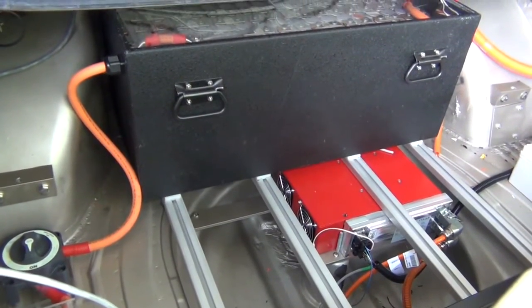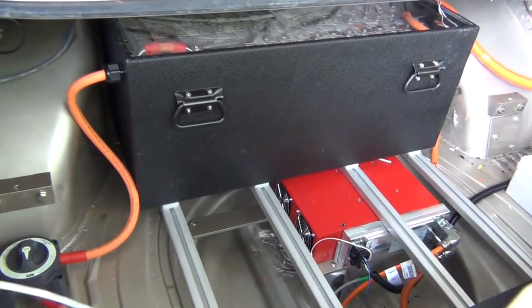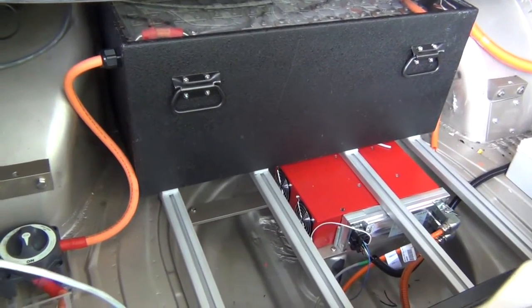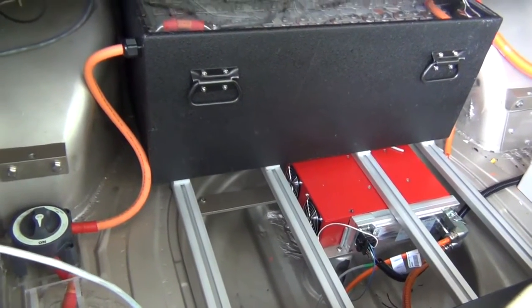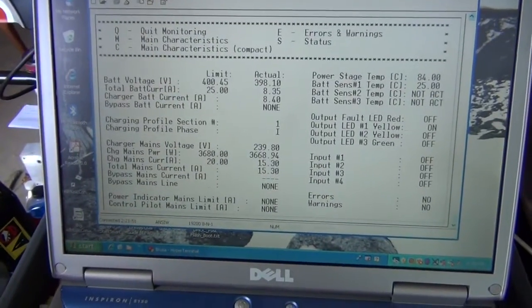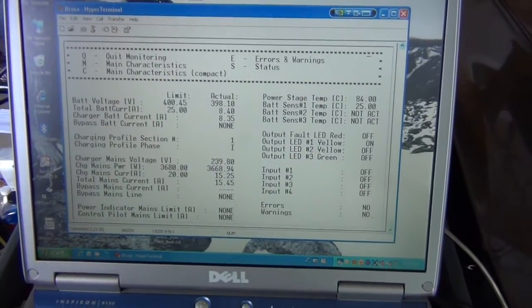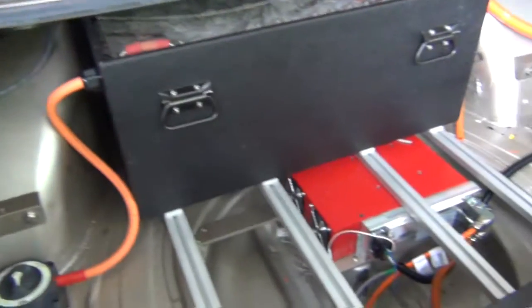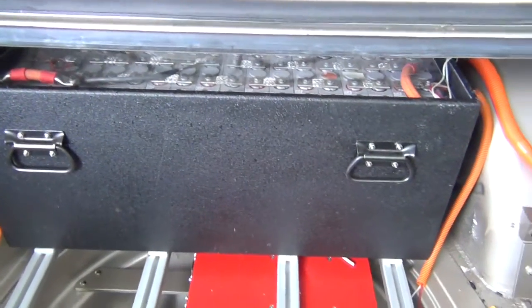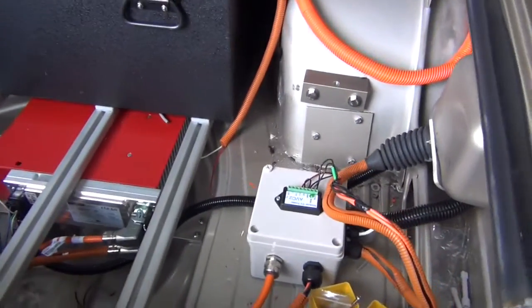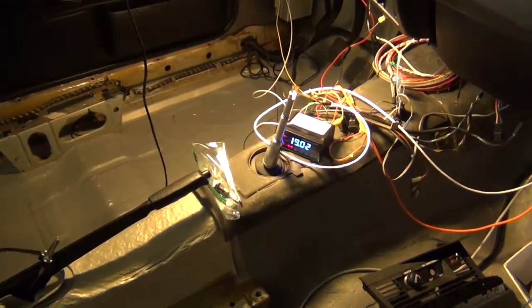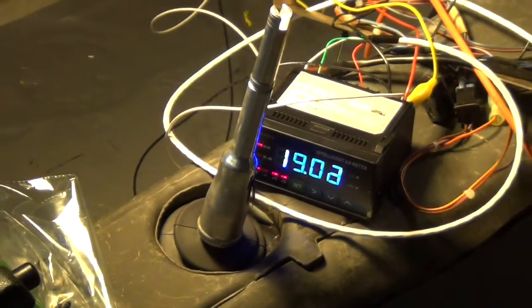After spending almost a week trimming up individual batteries to bottom balance them, I now have the whole pack connected and charging. It's up to 398 volts, and everything looks really good. There's no temperature rise. I've been checking individual battery voltages, nothing out of the ordinary, and everything in here is working well. Almost up to a third of the pack, 19 amp hours, so everything looks good.